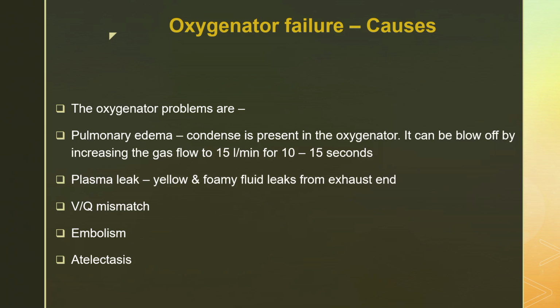Whatever oxygen is going through the gas phase is cold, so it gets condensated on the gas phase, and small water molecules are formed. When these water molecules form, they remain in the gas phase and decrease the sweep gas. So even if your sweep gas is set at 4 liters, the actual sweep gas going through might be only 3 liters because the space is occupied by water molecules. That is what we call membrane edema.